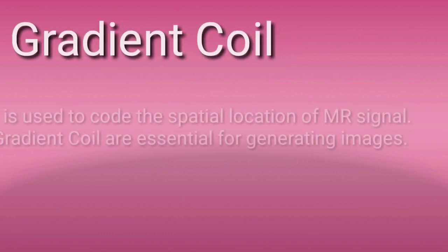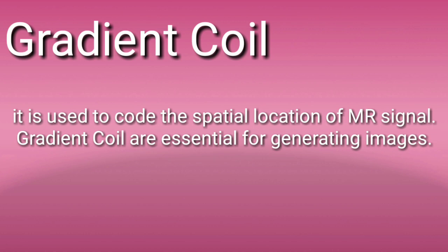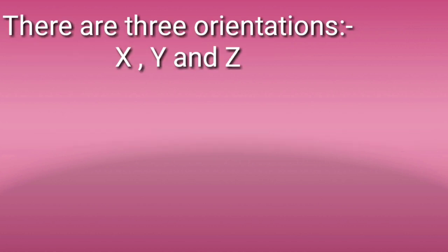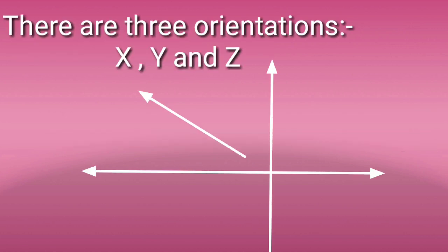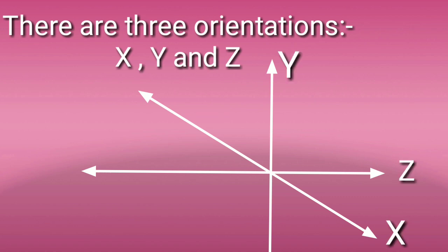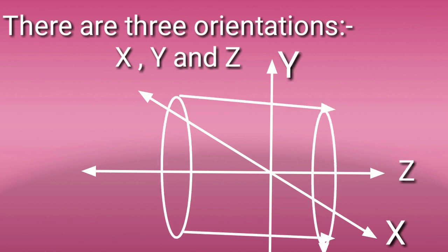Gradient coil is the coil of the MRI system. It is used for spatial location of MRI signals and is essential for generating images. There are three orientations used in the gradient: X, Y, and Z. Here you can see the diagram showing a patient lying along the Z axis.